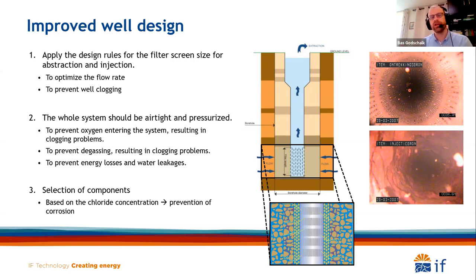We often abstract water from deeper aquifers, which contain dissolved iron. So you should prevent any oxygen or nitrate from entering your ATES system, because if oxygen enters, it reacts with the dissolved iron, causing a lot of iron precipitation. You can see on the right side a clean filter on top, from a camera inspection.